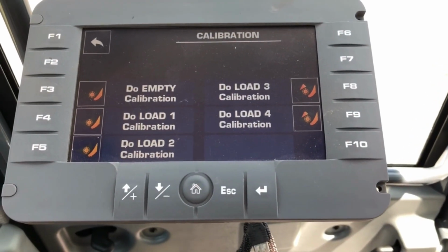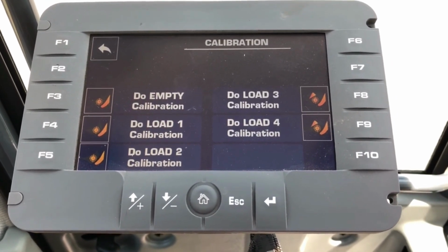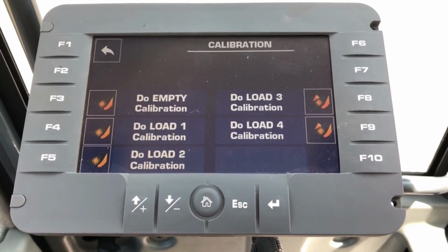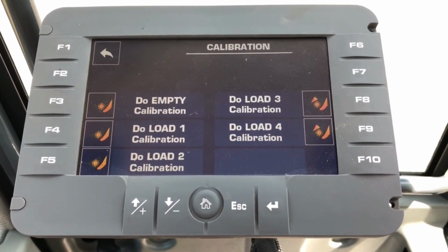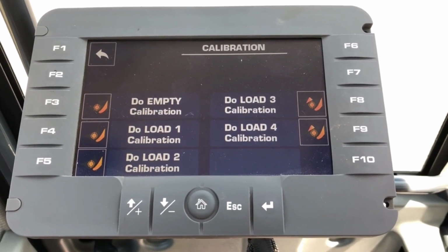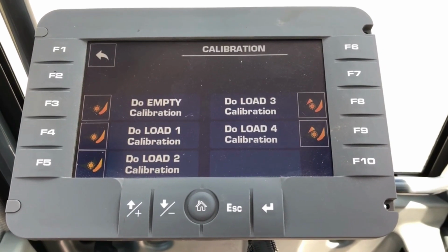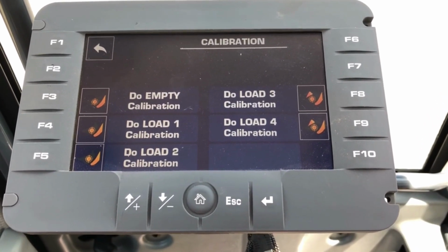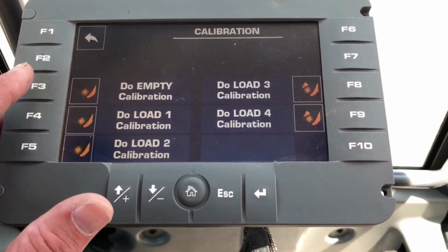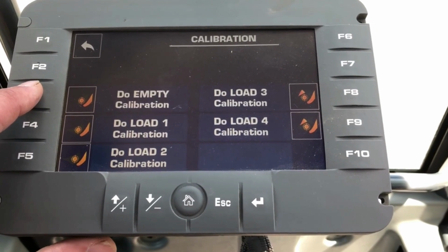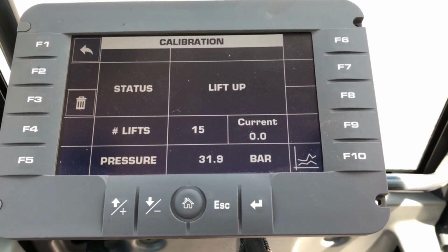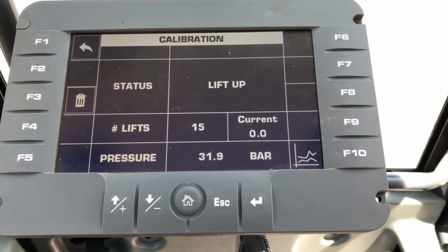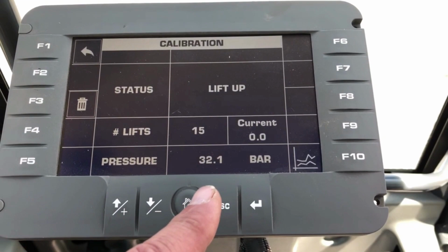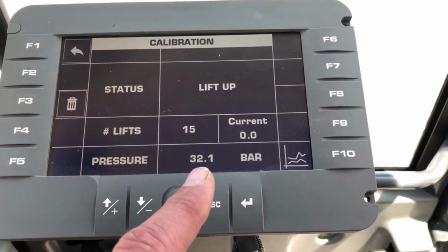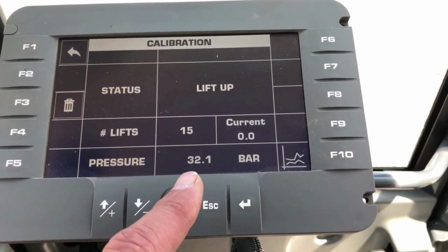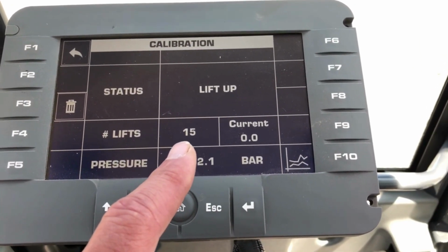And you can see it's going to come up to your different calibration points. Your empty cal, your first load, your second load, your third load, and your fourth load. Your first load will be your lighter of the loads, then you want to increase gradually up to about a full bucket for load 4. You can start with do empty calibration, so hit F3. It is now showing us the status, which is I want you to lift up, the number of lifts, and your pressure in the system. So there's currently 32 bar, and I already did 15 lifts.